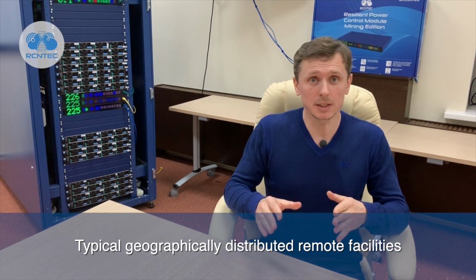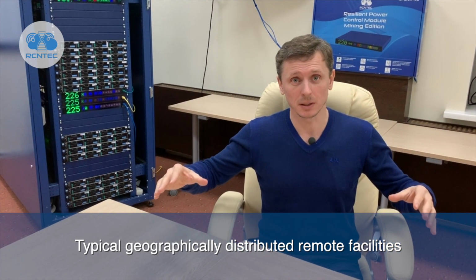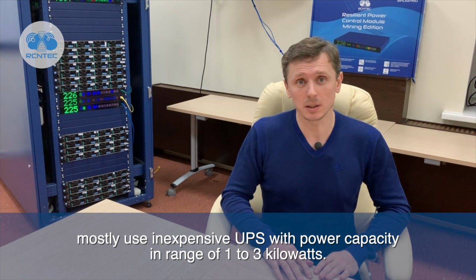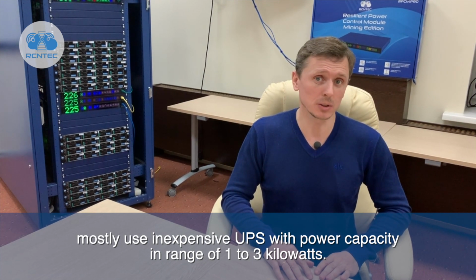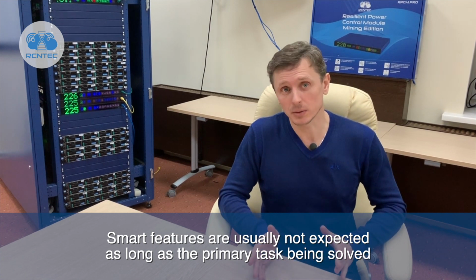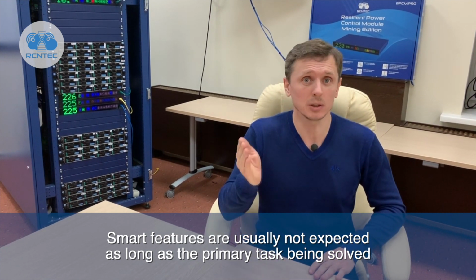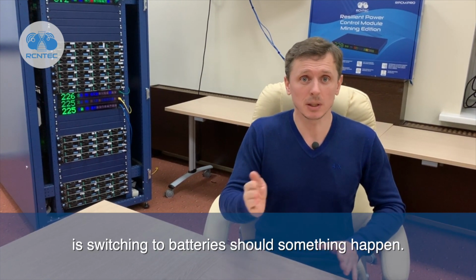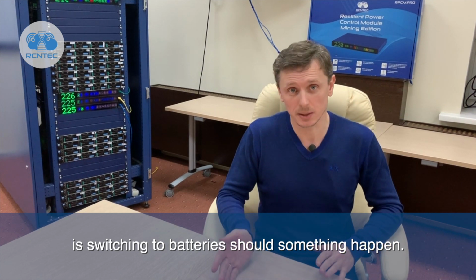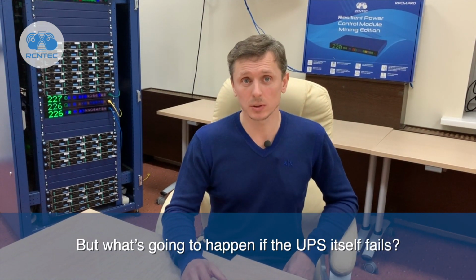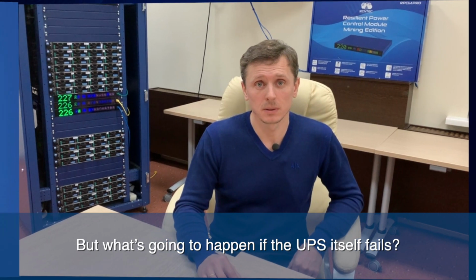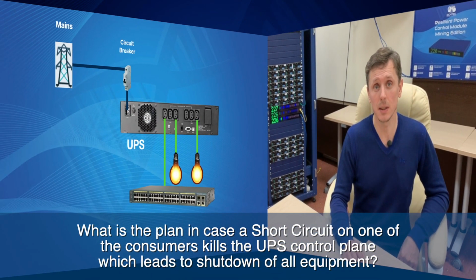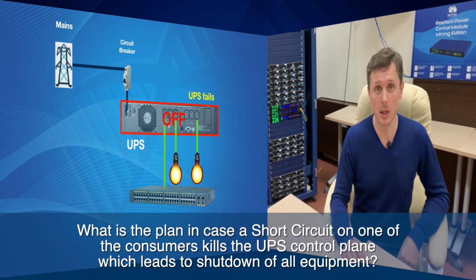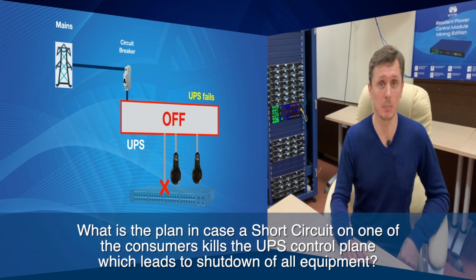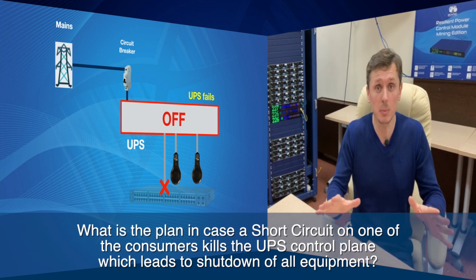Typical geographically distributed remote facilities mostly use inexpensive UPS with power capacity in the range of 1 to 3 kilowatts. Smart features are usually not expected as long as the primary task being solved is switching to batteries should something happen. But what's going to happen if the UPS itself fails? What's the plan in case a short circuit on one of the consumers kills the UPS control plane, which leads to shutdown of all equipment?